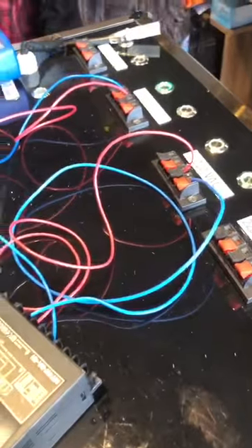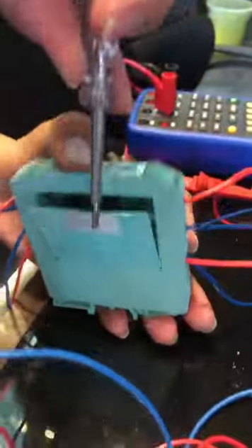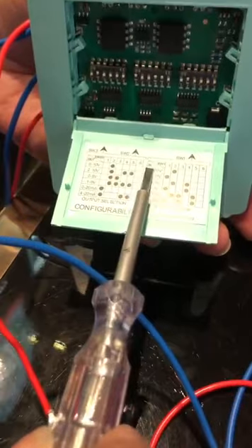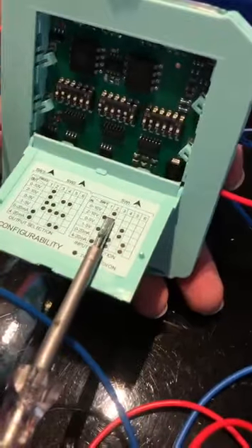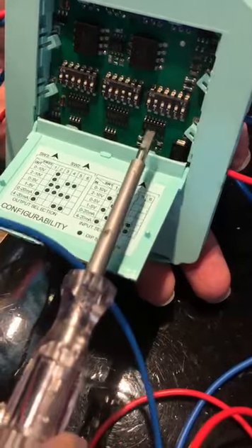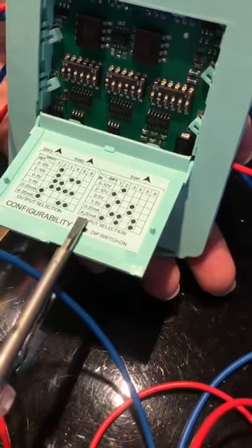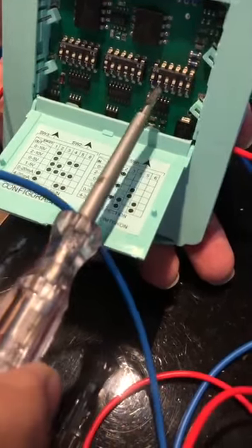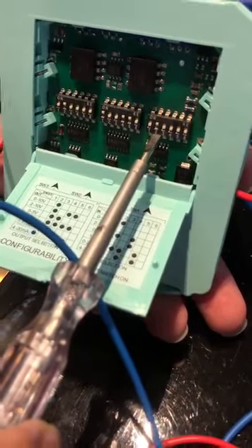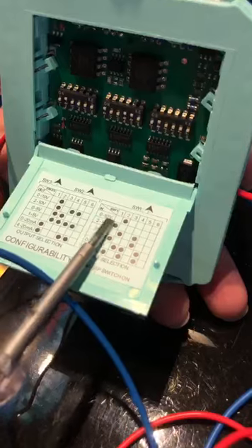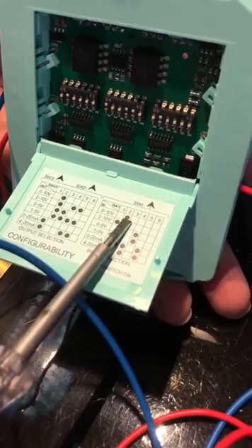So the system is okay. We're just going to open up this cover. We can see from here that switch number 1 stands for input. So input is switch number 1. We set that one as a 0 to 10 VDC input. You can see that my DIP switch configuration is that only the second DIP switch is on. For 0 to 10 VDC, only the second switch is on.